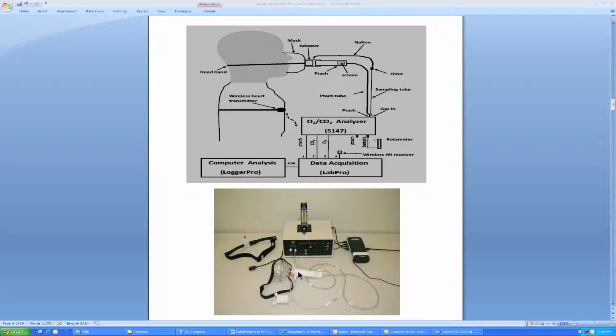The small adapter has a luer connector to which the sample line is attached. The sample line consists of the Nafion piece, the particulate filter, and a small piece of tubing connected to the gas in on the S147. The second larger piece of tubing, which is attached to the end of the PTAC, carries the differential pressure signal down to the PTAC input, where it will be measured to provide a measure of breath flow.